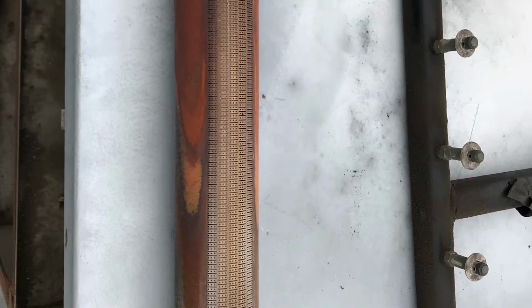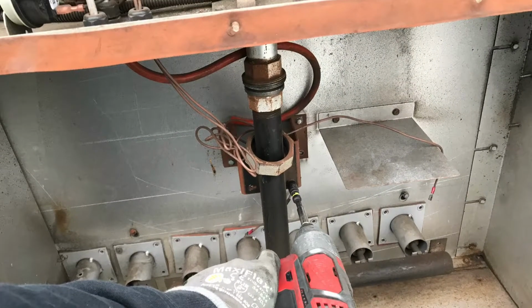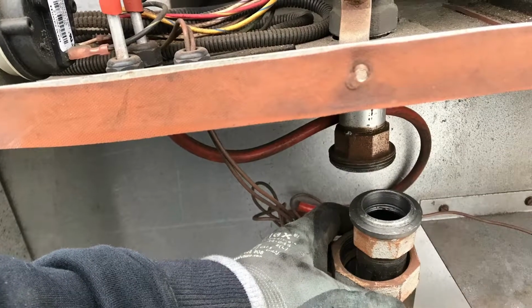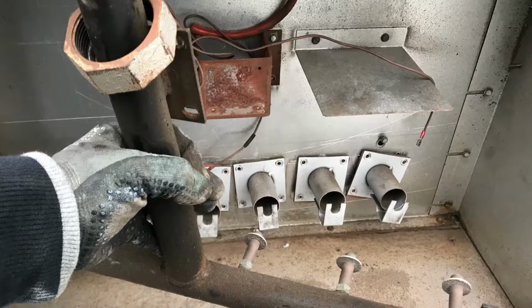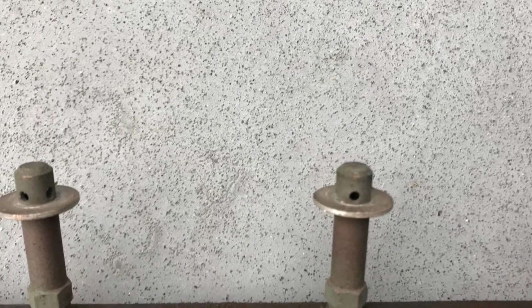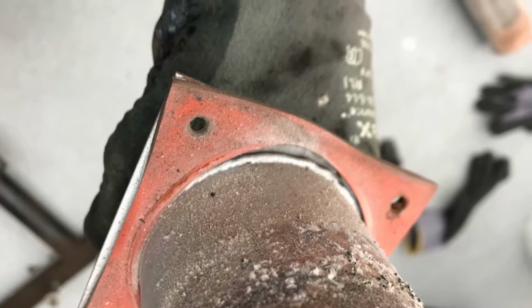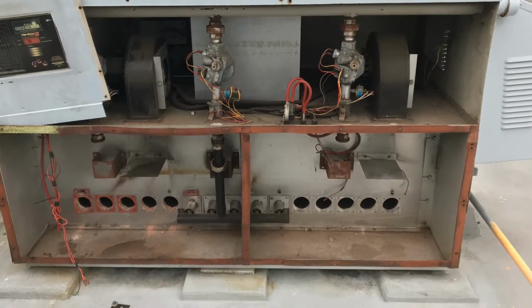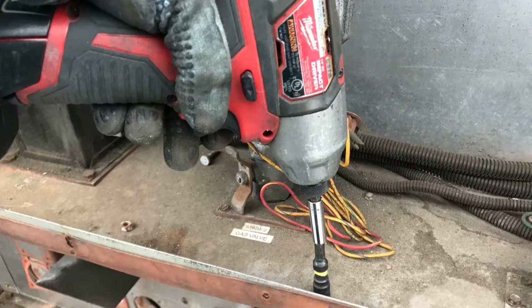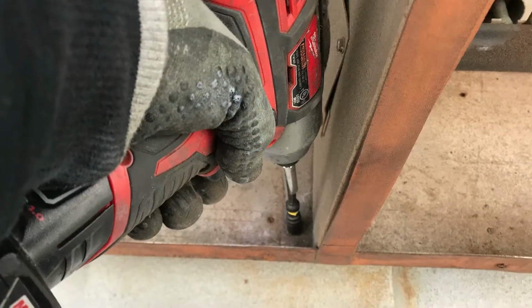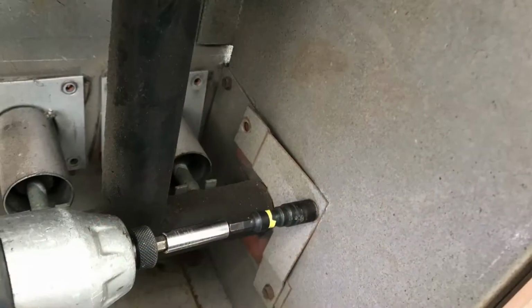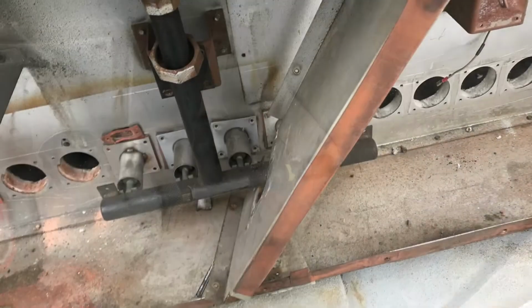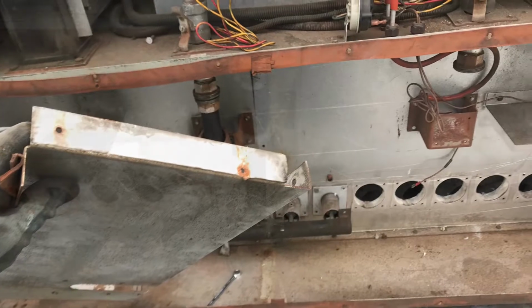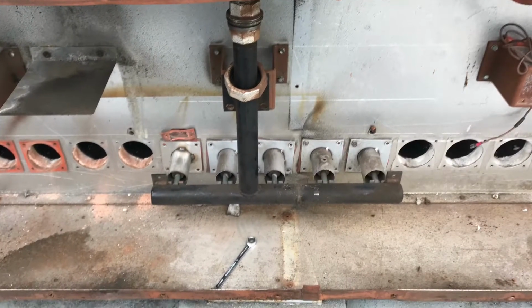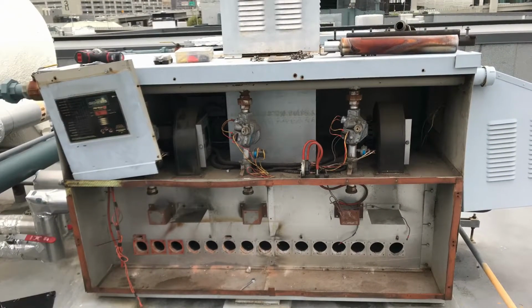Inspect all burners and headers for damage or cracks. Inspect the gaskets, replace if needed. And on this unit, you're left with the center header, which needs a little more work. So you will need to remove the center bracket, take all the screws off holding the center bracket. And then carefully, with a little bit of force, remove that center bracket. And once that center bracket's gone, now you have full access to the header. Remove the header. And now this is a picture of the unit without any of the burners or the headers.